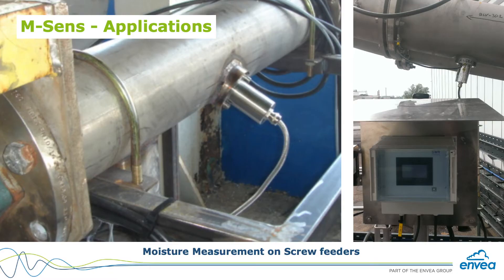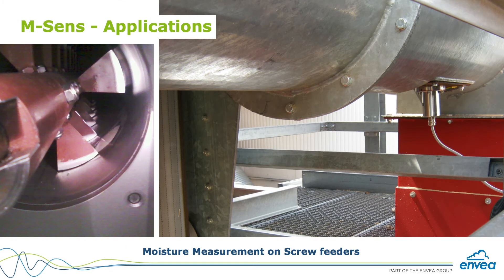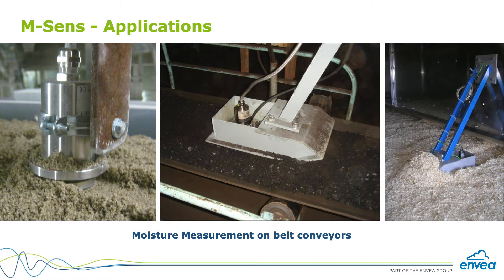Can I install an M-Sens in something that isn't a pipe or a free fall — can I put it on a conveyor belt or in a hopper? The M-Sens is always installed in points where the material is always moving. Think about a rotary feeder — the blades are always moving the material, so we place the sensor where material is always renewing. For a conveyor belt installation, the sensor should be installed facing down so the material flows touching the sensor surface from the bottom.